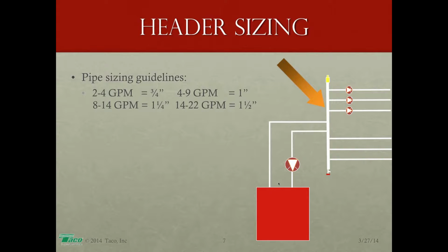Now there's that overlap between 1 inch and 1.25 inch. We have 4 to 9 gallons per minute for 1 inch, 8 to 14 gallons per minute for 1.25 inch, and that's just the difference in inside diameter between Type M copper and Schedule 40 black iron. You may not be using Schedule 40 black iron on something like this, but because the Schedule 40 has a smaller ID, you're limited to 8 gallons a minute on 1 inch black iron. You can go up to 9 gallons a minute on 1 inch Type M copper. So that explains the overlap. Okay. Now, a couple quick questions.